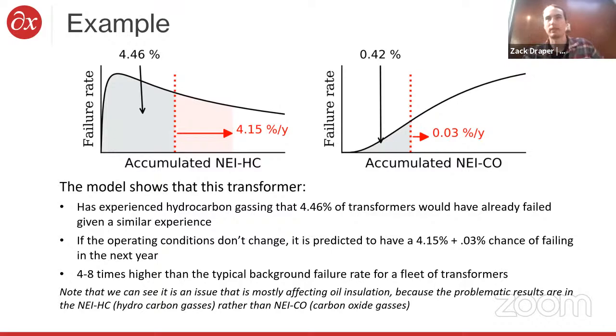That's the red arrow showing the hazard factor of an additional 4%. If you think about the background failure rate of transformers being on the order of 0.5% to 1% per year, then this is essentially 4 to 8 times that. So this would be a very risky transformer to be operating, and it really necessitates some kind of intervention - taking it offline, doing power factor testing, figuring out why it's gassing. It doesn't tell you exactly what to do, but it gives you a general sense of the risk involved in operating that transformer, and allows you to prioritize risky transformers over less risky ones.